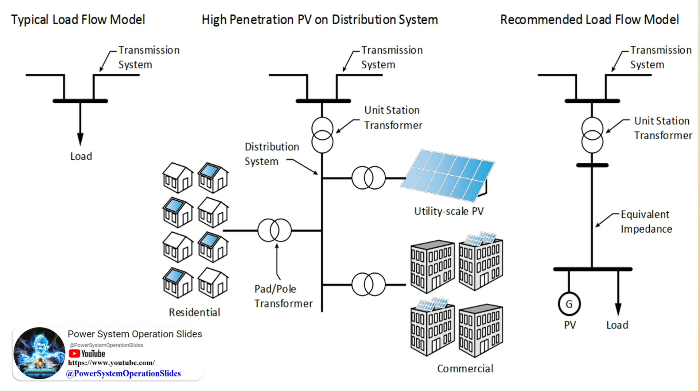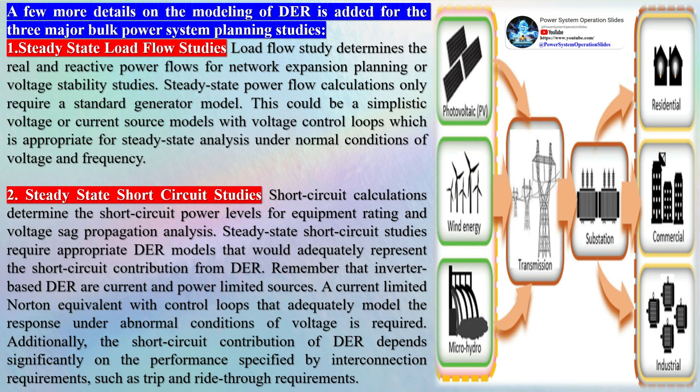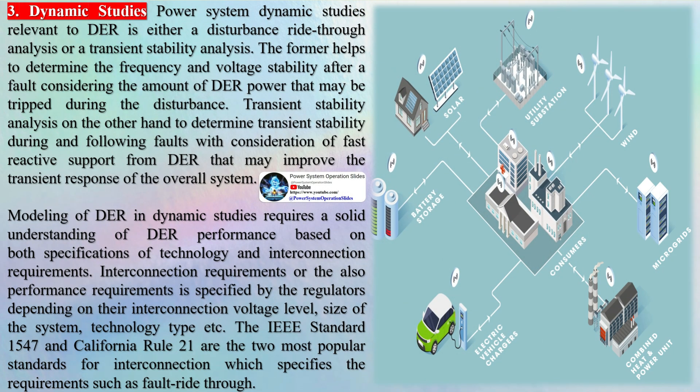Transient stability analysis determines transient stability during and following faults, with consideration of fast reactive support from DER that may improve the transient response of the overall system. From a power system operations perspective, the two most important value components are reliability and resiliency. Reliability is the ability to offer continued services, defined in terms of adequacy (enough generation to meet load) and security (ability to withstand disturbances). Resiliency augments reliability and views the grid as something more than currents and voltages. Transactive energy is a future-oriented valuation methodology — both a technical architecture and an economic dispatch system — that allows coordination of DER and enables them to be dispatched in response to price or other signals.